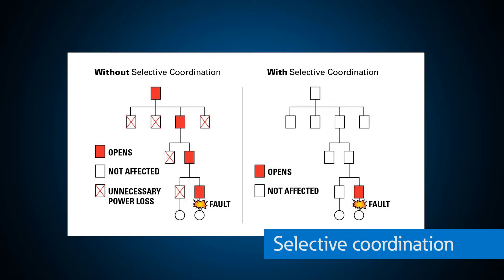The purpose of selective coordination is to increase the reliability and uptime of a power distribution system. Theoretically, a relatively minor downstream fault in a system that is not selectively coordinated could result in multiple breakers tripping on overcurrent and causing a widespread outage. Selective coordination is achieved by setting the overcurrent devices such that the device closest to the fault opens first, rather than all devices that see the fault current opening. This applies for the full range of overcurrents on a system. In other words, a short circuit fault can occur downstream with upstream circuit breakers experiencing but not tripping on the fault current, while only the circuit breaker closest to the fault opens. This is a key advantage of low voltage switchgear and why designers emphasize the three-cycle versus 30-cycle ratings.